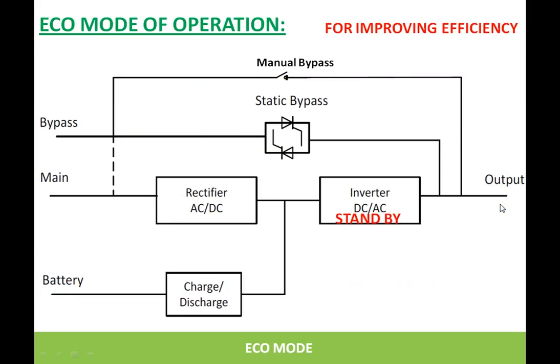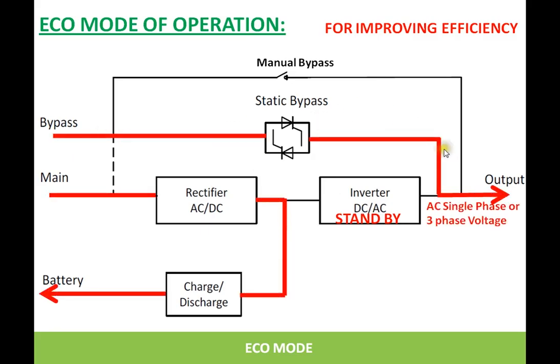The other mode is the eco mode of operation. Some UPS units have this mode for improving the overall efficiency of the UPS system. The inverter's job is converting DC to AC, and this operation is not 100% efficient because there are losses during conversion. In order to improve efficiency in this mode, the inverter is kept in standby under normal conditions. Whenever incoming power is available, the output is fed through the static bypass switch while the inverter is on standby, so there are no losses in the inverter.